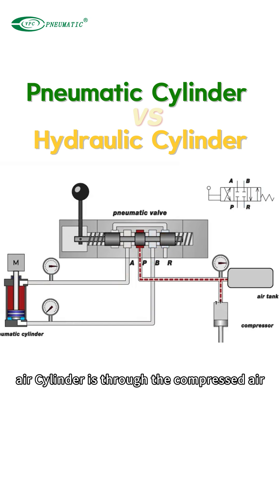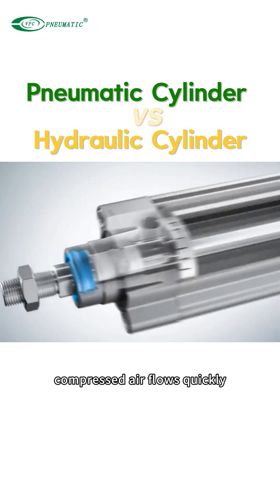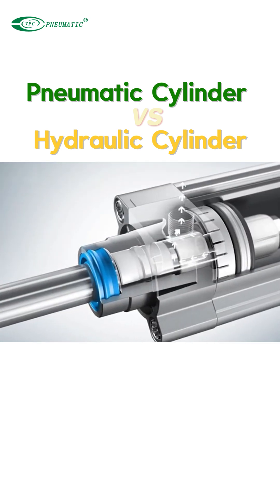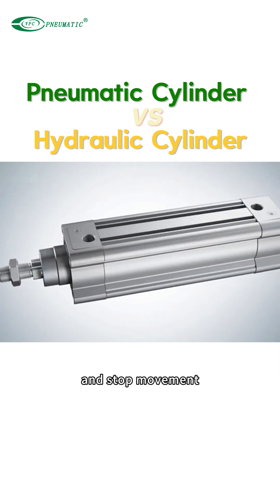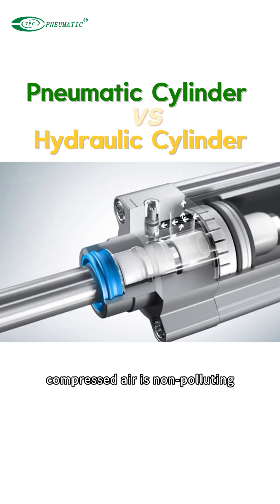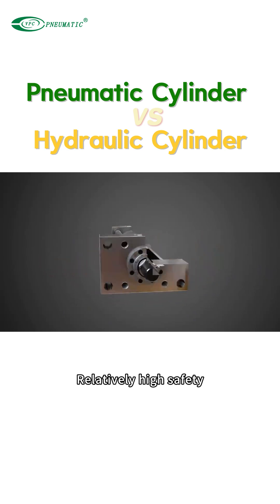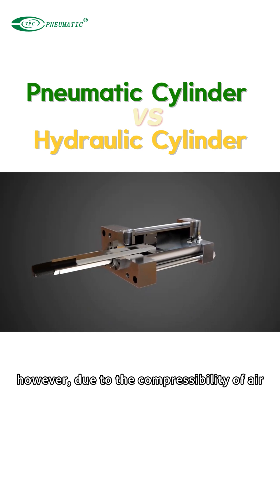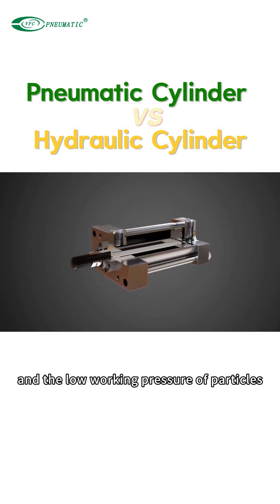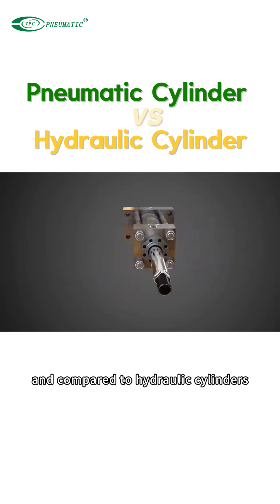The air cylinder drives the piston through compressed air. Compressed air flows quickly, allowing the cylinder to quickly start and stop movement. Compressed air is non-polluting, less likely to leak or explode, and has relatively high safety. However, due to the compressibility of air and the low working pressure, the output force is usually small.